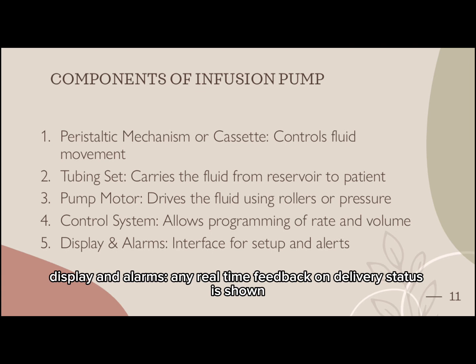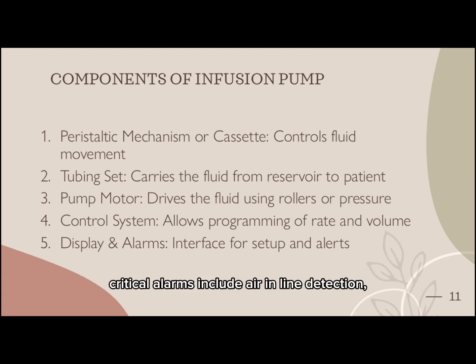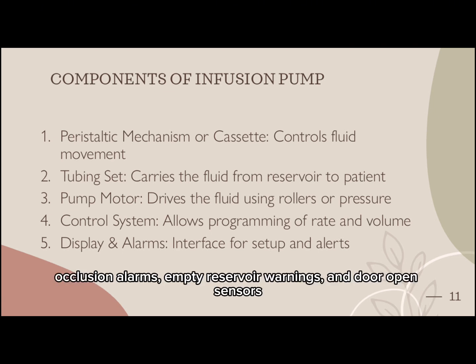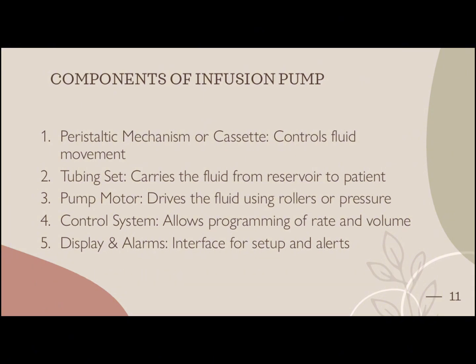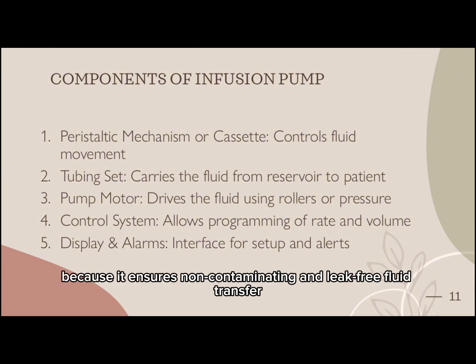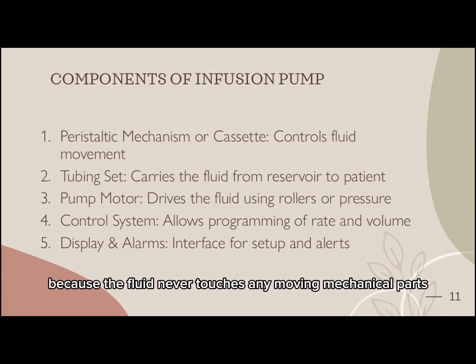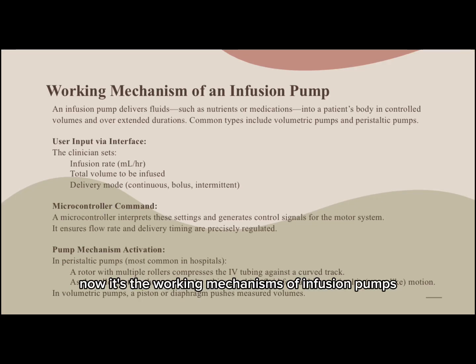Any real-time feedback on delivery status is shown. Critical alarms include air in line detection, occlusion alarms, empty reservoir warnings, and door open sensors. Most of the time, peristaltic motion is preferred because it ensures non-contaminating and leak-free fluid transfer, because the fluid never touches any moving mechanical parts.